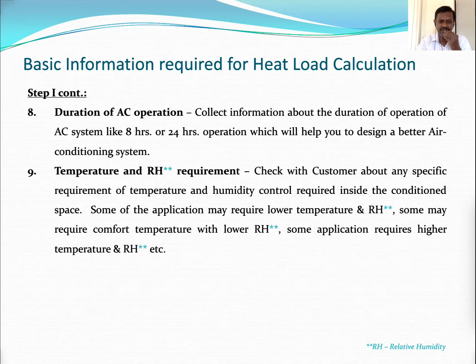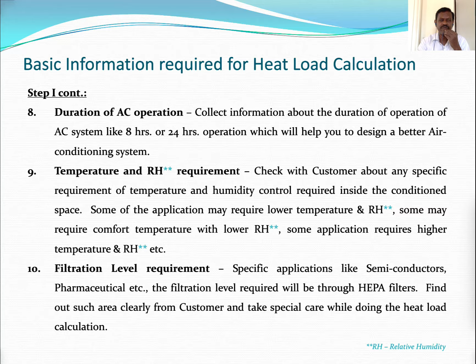Next is filtration level requirement. For industrial applications, some clean rooms, when we are talking about clean rooms, you have to find out the filtration level from the client, whether they want class 1 lakh or 10,000, 1,000, 100, 10, etc. Accordingly, you can design the entire AC system very precisely. So this information is also basic information that you have to collect before starting your heat load.